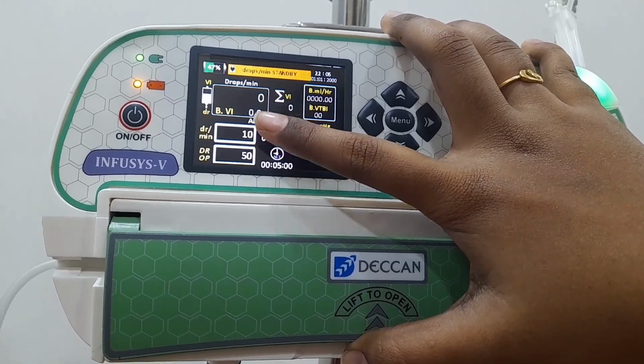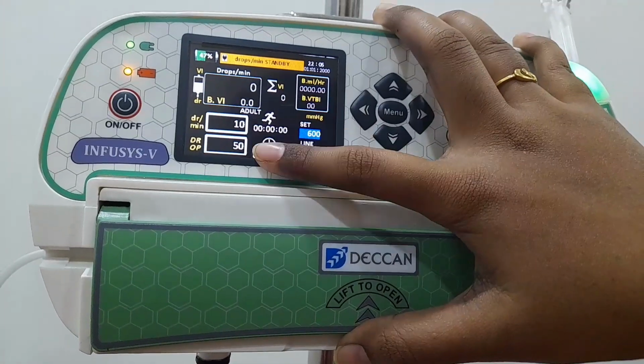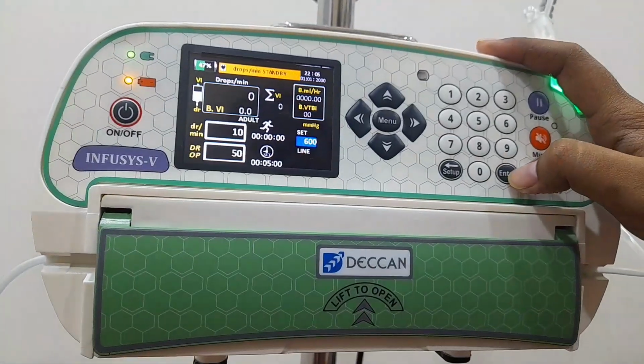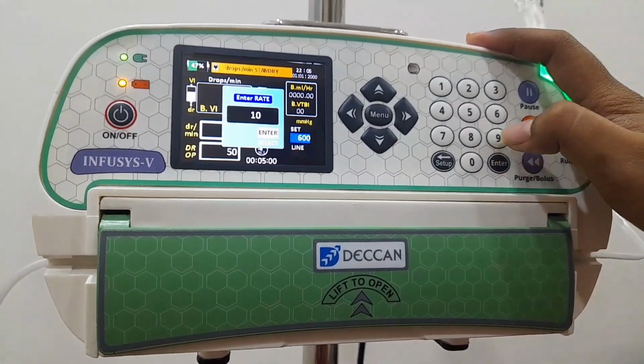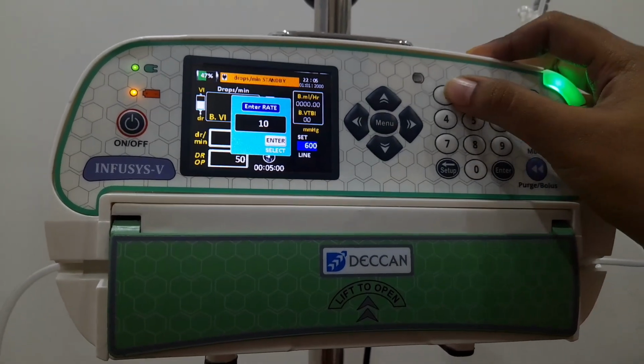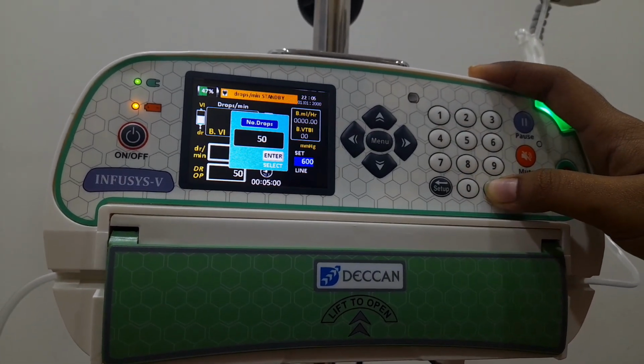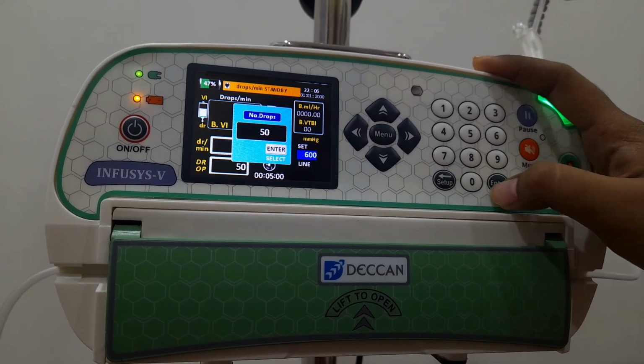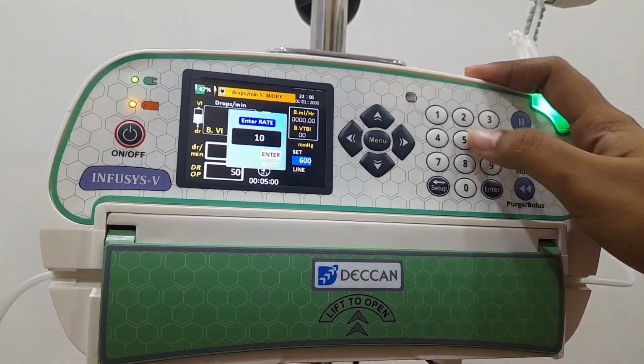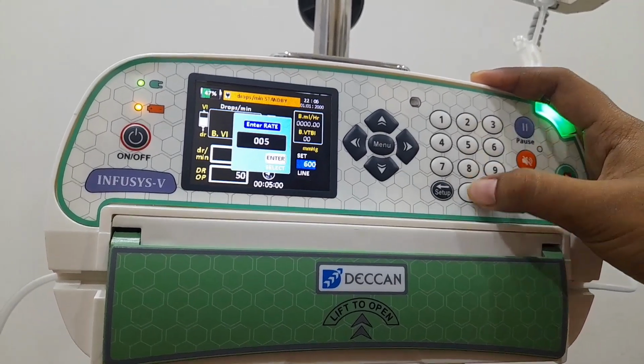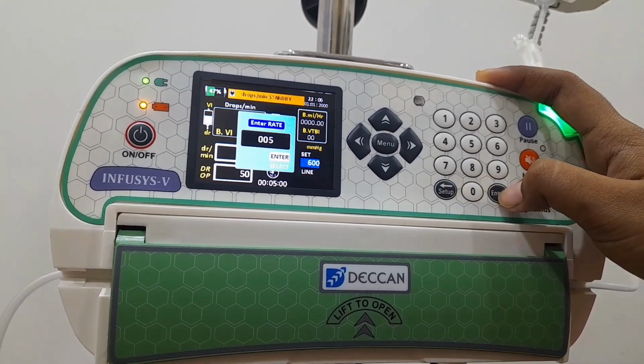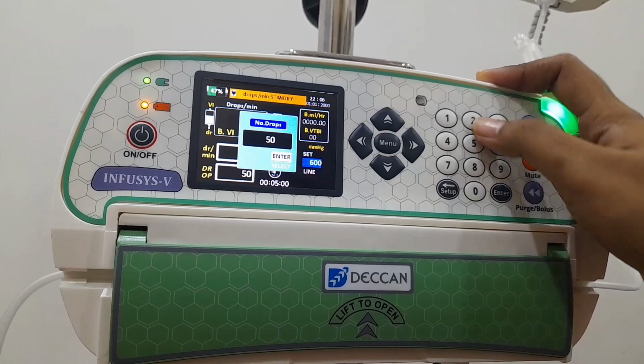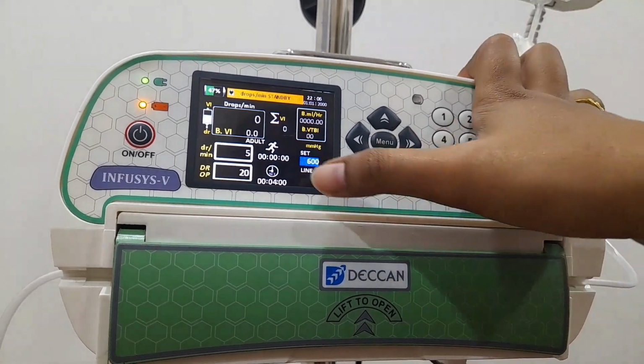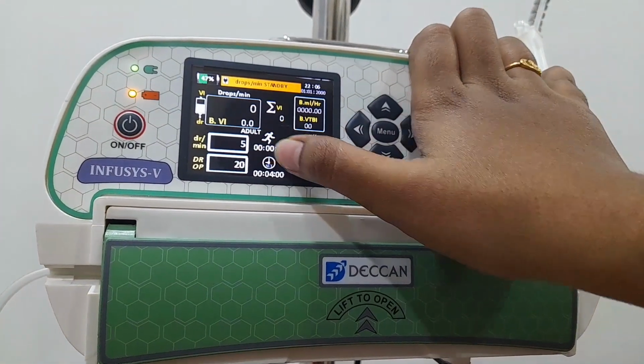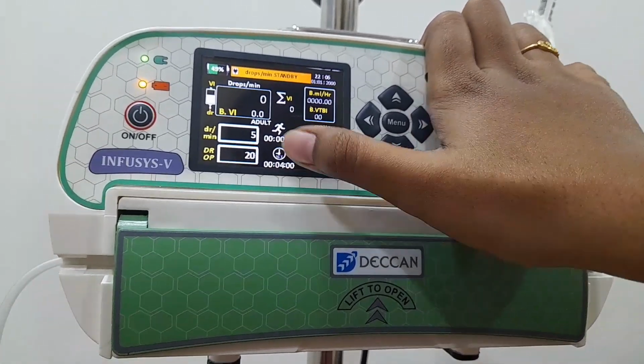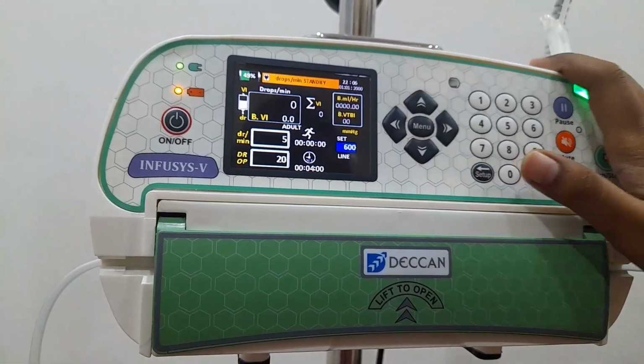Next we select the drops per minute and drops. So it is a rate as well as VTBI as per IV mode. Enter the rate as 5 and enter drops as 20. Based on that, the calculated time will appear on the screen. Here we selected 5 drops per minute and 20 drops to deliver. So the calculated time is 4 minutes. Within 4 minutes we reach the targeted volume of 20 drops.